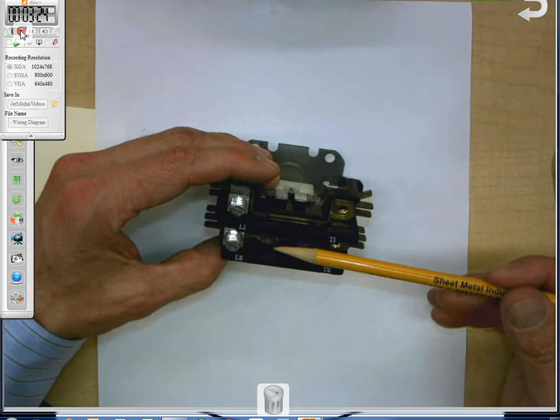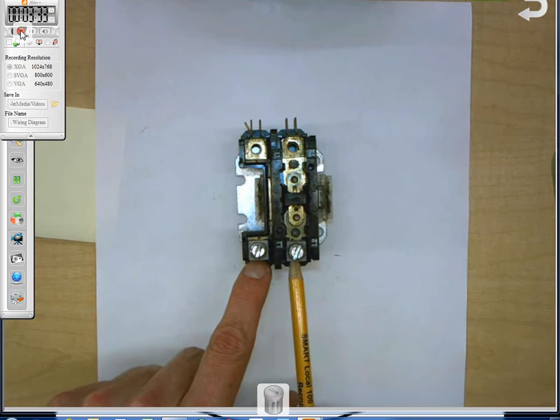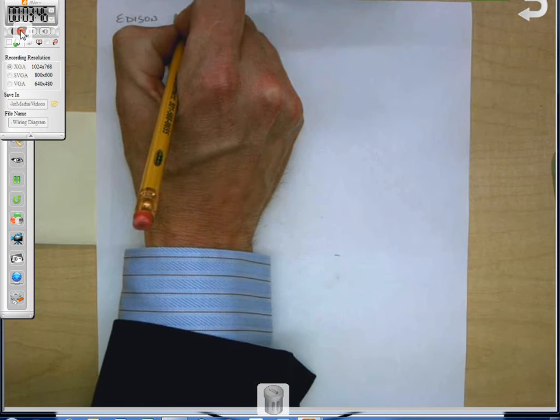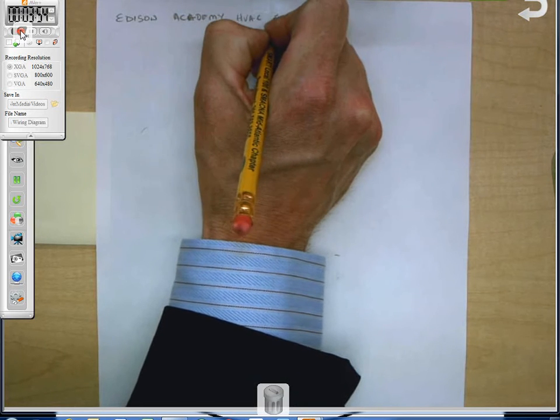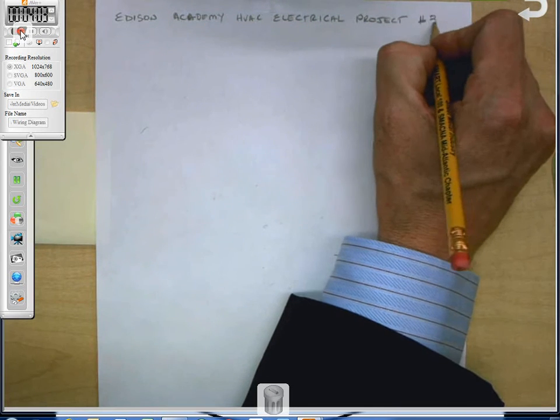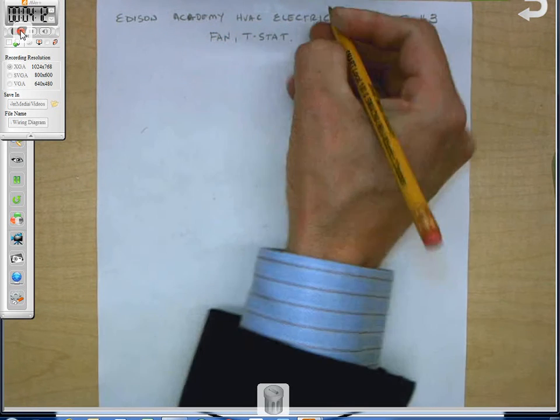We have a 24-volt coil on our contactor here, and we have 240 volts able to go through the contacts. L1, L2 is where it's coming from our breaker or disconnect, and T1, T2 is where it's going to the load, or in this case, our fan motor. So we're going to go ahead and draw it, so let's go ahead and title it up. Ready? Everybody title it up. Edison, this is Edison Academy HVAC Electrical Project Number 3.